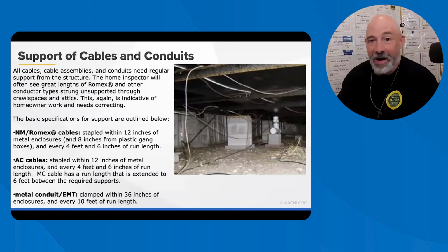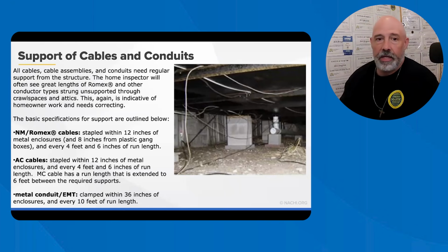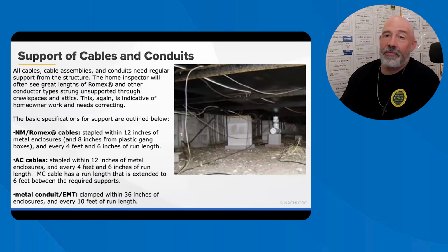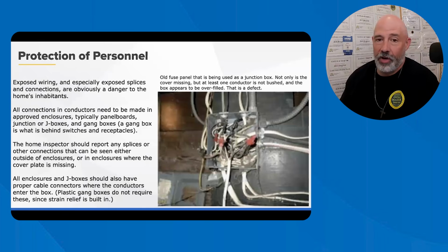Yeah, I was just talking about that. Within 12 inches of metal boxes, make sure that it's 8 inches if it is plastic boxes. And again, like I said, just kind of eyeball it. You don't have to be perfect, but as long as it's somewhere around there. Every 4.5 feet, it should be stapled in. The AC cables within 12 inches and 4.5 feet, same thing. The MC cables within 12 inches of the box and every 6 feet. The EMT conduit within every 36 inches of the box and every 10 feet along that. Long support runs are often signs of improper installation and should be reported for further evaluation.